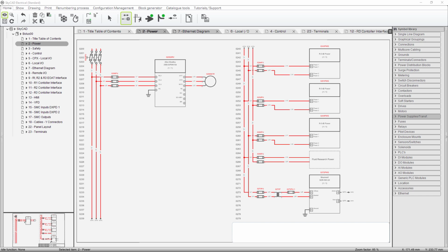and it shows power going through fuses. Then we have the epoxy dispense system, fluid research power, that is a pre-built, already functioning, commissioned two-part mixing system that you program what size shot you want, you put in a request, it pumps out that size, and then it stops. So it's a completely separate machine with its own PLC. And the reason that I'm running power to that epoxy dispense is because the epoxy dispense sits right by the cell. It has an e-stop on it, and if we hit the e-stop on the main machine, the main panel, we want the fluid research to stop as well. And if we hit the one on the fluid research, we want the main one to stop as well. So as long as we're doing that, we're running the power through the disconnect and the main panel to the panel that came with the epoxy dispense. And of course we have two fuses to do that.